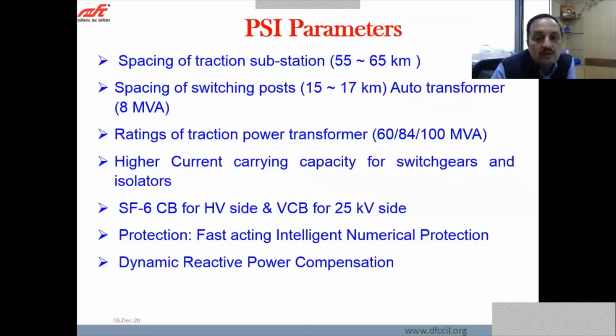just listening, somebody was asking about the power quality aspects from NCRTC. So I can make it very clear that here DFCCIL has been using dynamic reactive power compensation so as to ensure the power quality parameters are within the limits, and we do not pay a single penny of penalty on account of low power factor or any harmonics in the system. So DFCCIL is taking care of all this with the adoption of dynamic reactive power compensation.